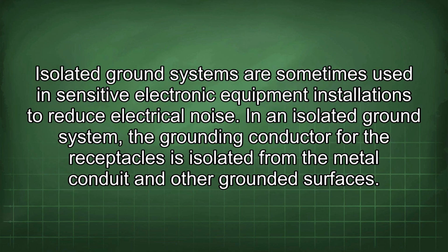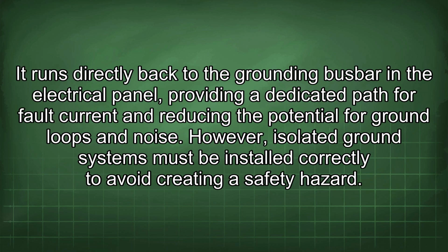Isolated ground systems are sometimes used in sensitive electronic equipment installations to reduce electrical noise. In an isolated ground system, the grounding conductor for the receptacles is isolated from the metal conduit and other grounded surfaces. It runs directly back to the grounding busbar in the electrical panel, providing a dedicated path for fault current and reducing the potential for ground loops and noise. However, isolated ground systems must be installed correctly to avoid creating a safety hazard.